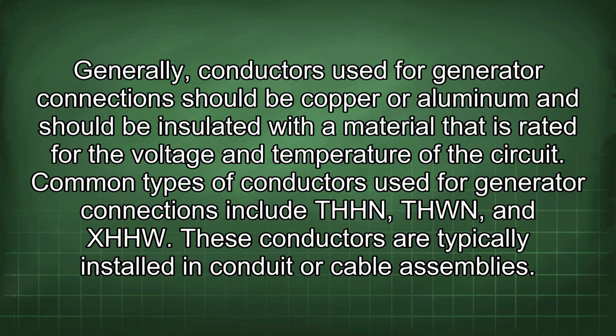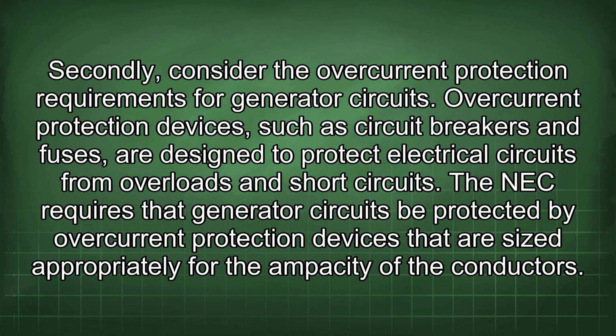Common types of conductors used for generator connections include THHN, THWN, and XHHW. These conductors are typically installed in conduit or cable assemblies. Secondly, consider the overcurrent protection requirements for generator circuits. Overcurrent protection devices, such as circuit breakers and fuses, are designed to protect electrical circuits from overloads and short circuits.